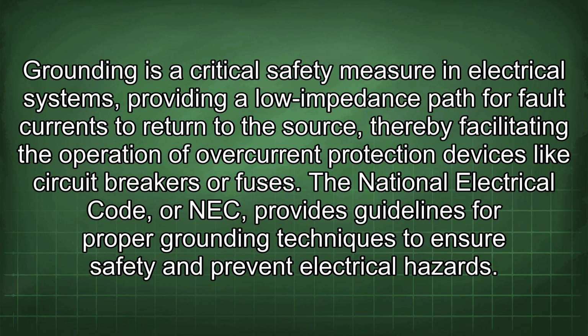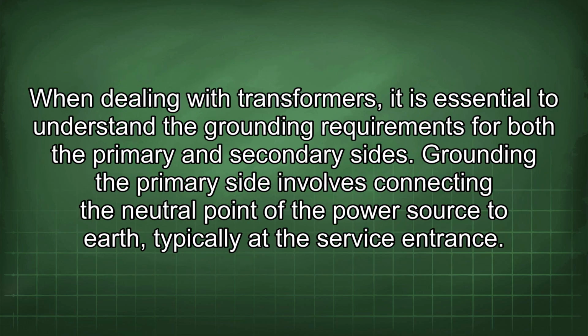Grounding is a critical safety measure in electrical systems, providing a low impedance path for fault currents to return to the source, thereby facilitating the operation of overcurrent protection devices like circuit breakers or fuses. The National Electrical Code, or NEC, provides guidelines for proper grounding techniques to ensure safety and prevent electrical hazards. When dealing with transformers, it is essential to understand the grounding requirements for both the primary and secondary sides.